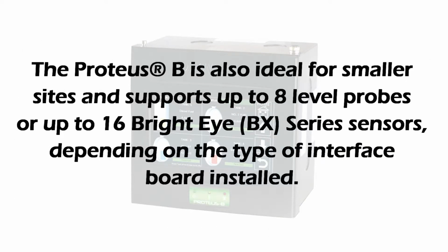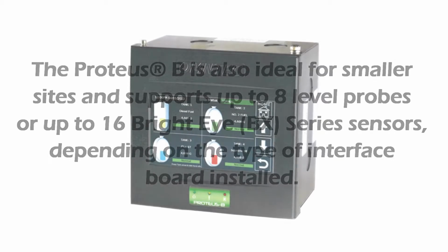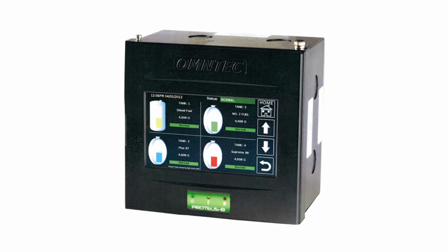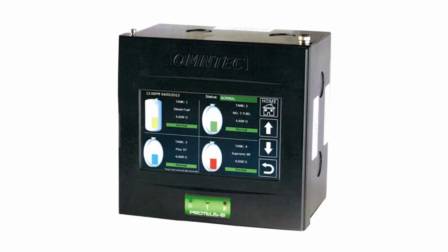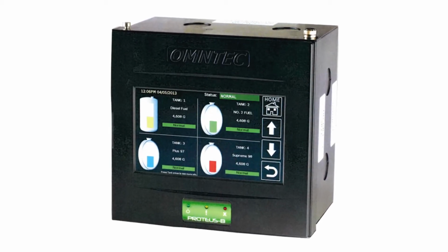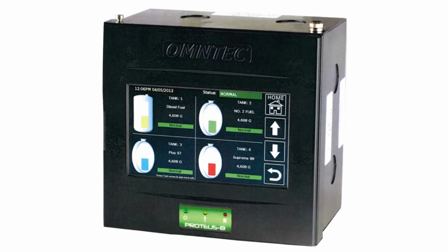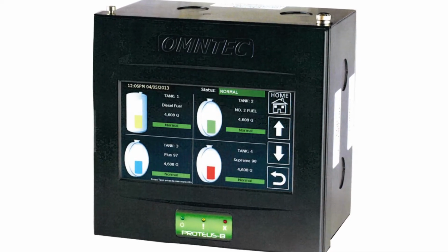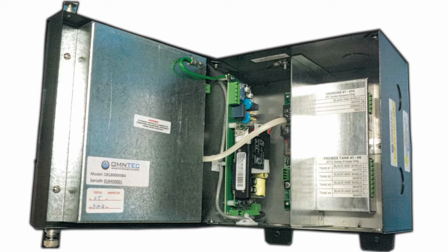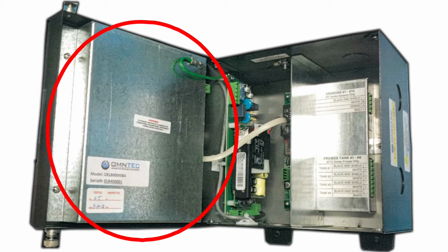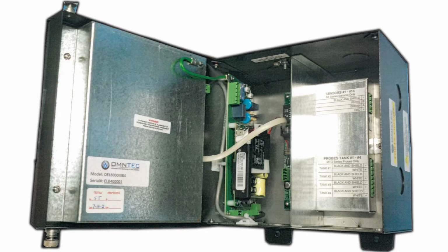The Proteus B is also ideal for smaller sites and supports up to 8 level probes or up to 16 bright eye series sensors, depending on the type of interface board installed. Unlike the Proteus X or Proteus K, the front panel has only our 7-inch color touchscreen display. The Proteus B is not equipped with a printer. Looking on the inside, we see the back of the display has an intrinsic cover. On the left side of the controller is mounted the unit's power supply.